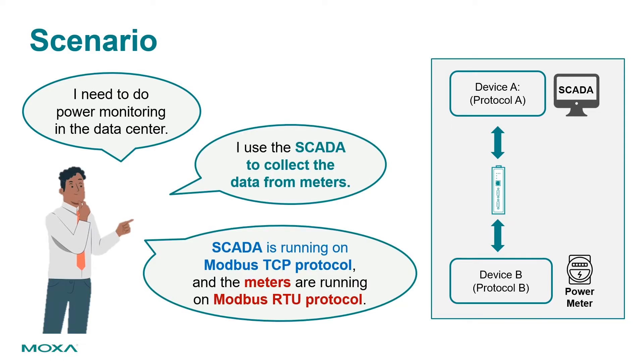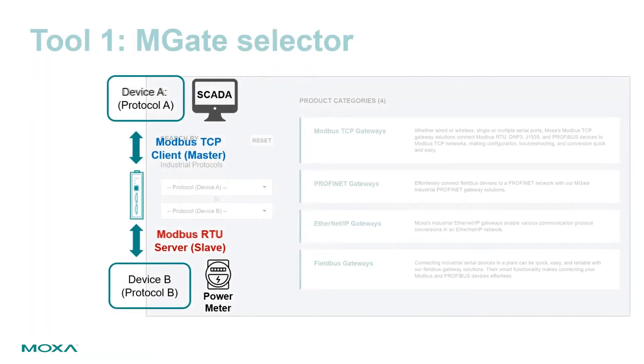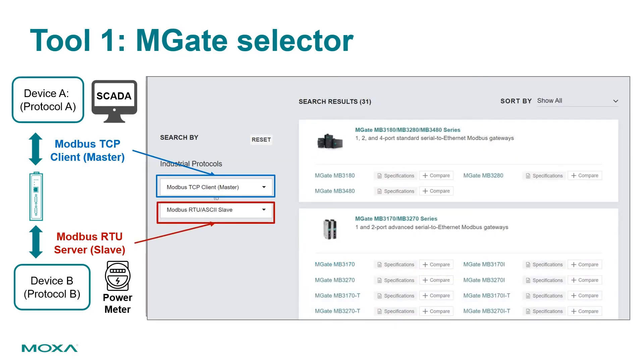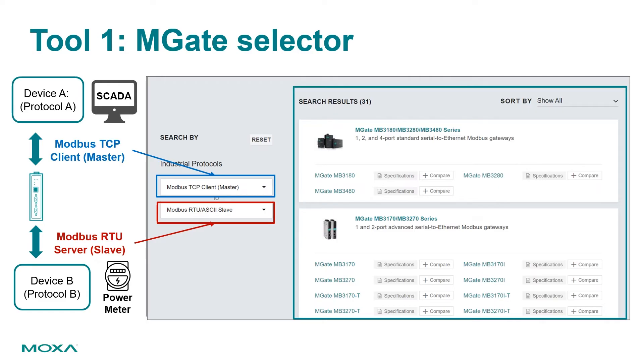SCADA is running on Modbus TCP protocol and the meters are running on Modbus RTU protocol. When using the online M-Gate selector, select Modbus TCP client in the field of device A, and select Modbus RTU server in the field of device B. Finally, check the search results to find suitable M-Gate models.